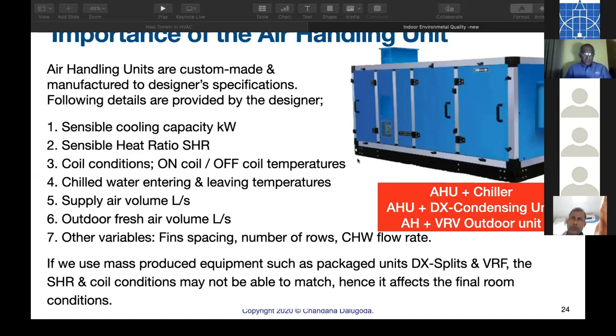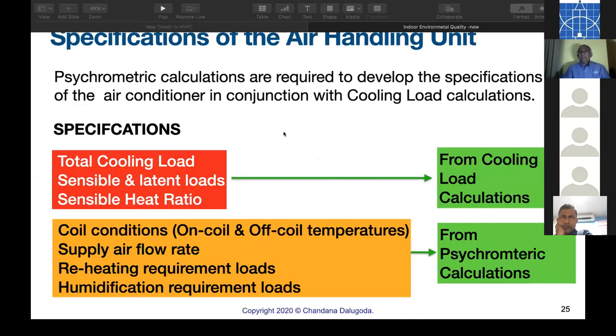These are the specifications. We give them sensible cooling capacity, sensible heat ratio, cooling coil entering and leaving, chill water entering and leaving, supply air volume, and outdoor fresh air volume. Sometimes we give fin spacing, number of rows, and chill water flow rate. There are so many variables, but we don't need to give all that. We need only air flow rate and entering and leaving conditions. But we have to give them advice when you insert this into the computer program: please don't keep the air conditioning capacity constant. Let it be variable, but the constant should be your entering and leaving conditions. So the air handling unit is the best air conditioner.